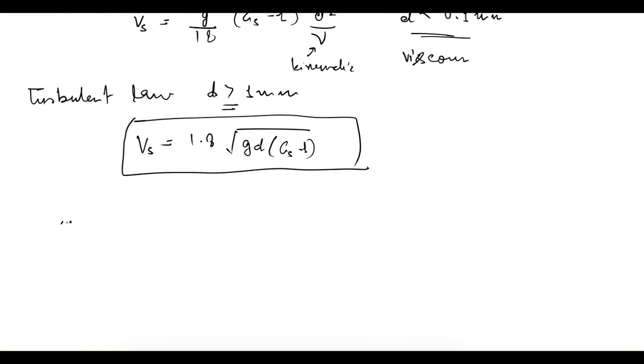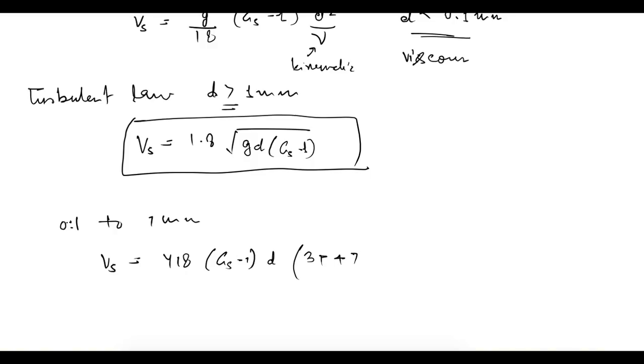If it is a transient flow — meaning particle size is between 0.1 mm and 1 mm, between laminar and turbulent — then the velocity of settlement is given as: Vs = (418 × (GS − 1) × d × (3T + 70)) / 100, where T is temperature in degrees Celsius.